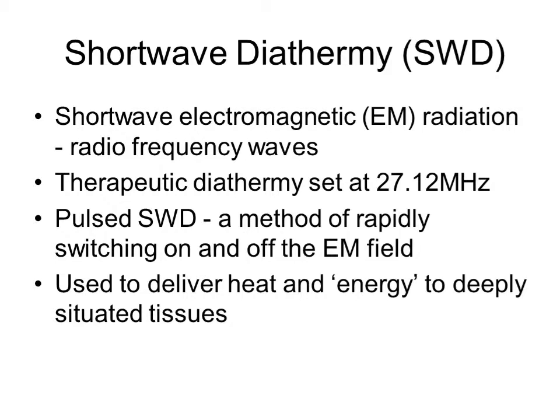Shortwave describes the wavelength of radiofrequency waves. For therapeutic use, this wavelength is set at 27.12 MHz. It is a rapidly alternating current, alternating between positive and negative charge at this frequency. Pulsed shortwave diathermy, as with pulsed ultrasound, describes the rapid switching on and off of the electromagnetic field.